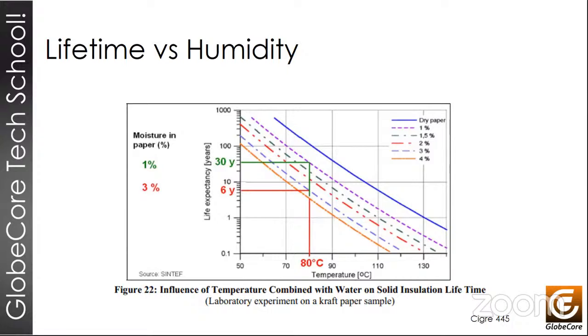So if we, in addition to temperature, also have water, things become a little more complicated. But let's take the value of 80 degrees. If the moisture content of the paper is 1%, the dashed purple line, the remaining life of the transformer is 30 years. And that's a very good value because transformers are usually rated for 20-25 years of operation. And if we can manage to bring it to 30 years, we get the best performance, actually. In fact, if we can lower the temperatures, we could extend the lifespan of a transformer theoretically over 100 years.